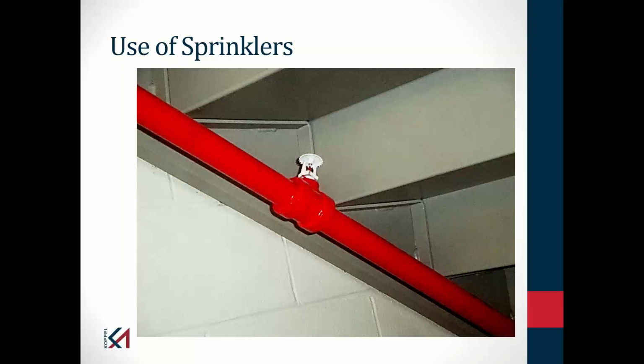Now, it's not necessarily easy to see on this photo, but you do see a relatively small glass bulb. If you look around some of the buildings on campus, you may see glass bulbs that are close to about 3/8 of an inch in diameter. That sprinkler is going to be a standard response sprinkler. When we get down to a 5 mm glass bulb, that could be a fast response sprinkler. At the 3 mm bulb, it probably is a fast response. The way I know is by the listing of the sprinkler. And for quite a while now, NFPA 13 has required something called a sprinkler identification, SIN number. It would be on this sprinkler, it'd be on the top of that deflector. And I can punch in that sprinkler identification number, even if I don't know the manufacturer, although part of this sprinkler identification number should tell you the manufacturer.